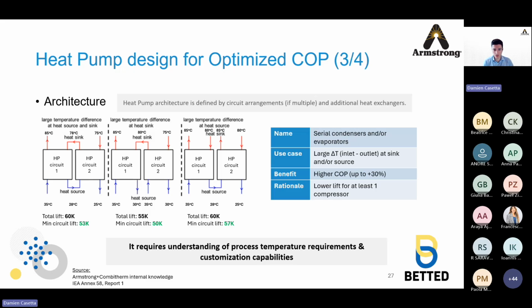And the rationale behind it is to lower the temperature difference on at least one compressor. So if you don't use it, in this example, you have a temperature difference which is 60. If you use it, the optimized compressor will have 50. And remember, that difference is driving the COP. So that's really key, and that can drive high benefits. But it requires understanding process temperature requirements very well, so you have all of those temperatures right. And it requires customization when you design the heat pump so you can adapt to the process and not vice versa.